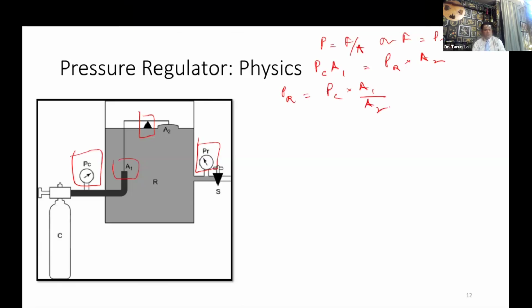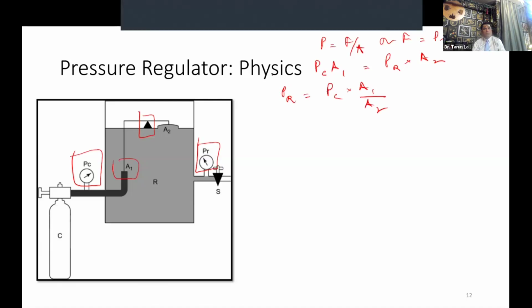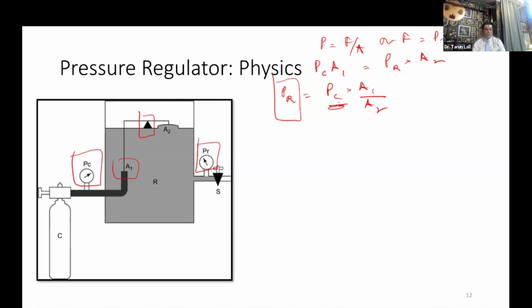But as you can also make out, there is a problem with this. As the pressure in the cylinder keeps on falling, the output pressure will also keep on falling. So the anesthetist will have to be very vigilant. As the cylinder pressure keeps on falling, you will just have to keep on increasing the flow, turning the flow control knob, adjusting the flow, and obviously that is quite a cumbersome deal. So what did the engineers do to help us solve this problem?